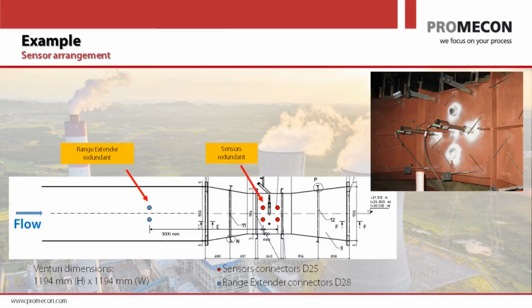Here's another example. That's a Mitsubishi Hitachi boiler in Duisburg. Here the system was planned in from the beginning. Why do they still have a venturi? Well, it's a very new technology for them back then. And they said, we will put in a venturi because that's the major work, but we will not put in a delta pressure measurement. We'll put the Promecon system in. But if it fails, then we might fall back to the delta P. I mean, that's redundant thinking of engineers. But needless to say, the system is still working today. It came in 2008, so now we have 2025. Still working, customer very happy, absolutely positive reference, like all of the ones that we have done on airflows.